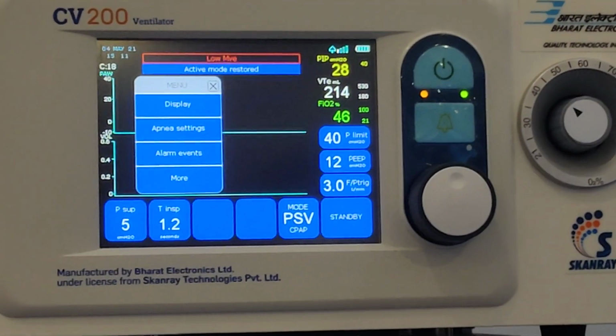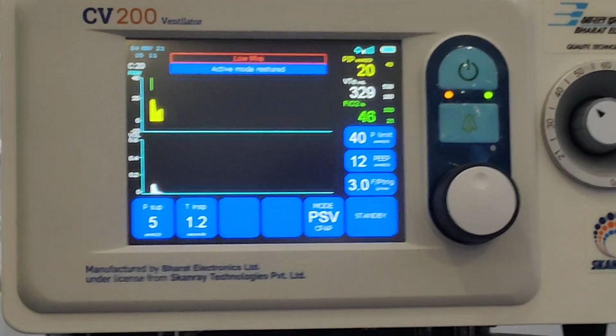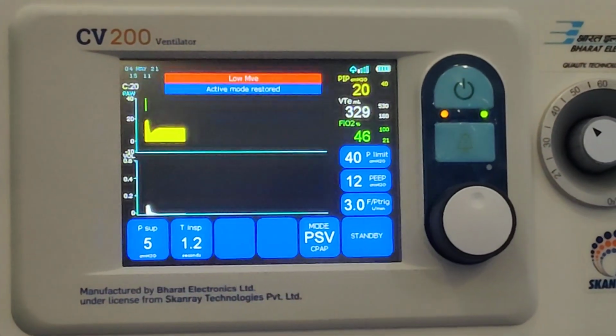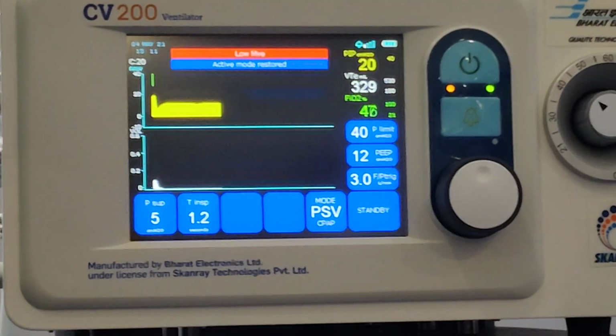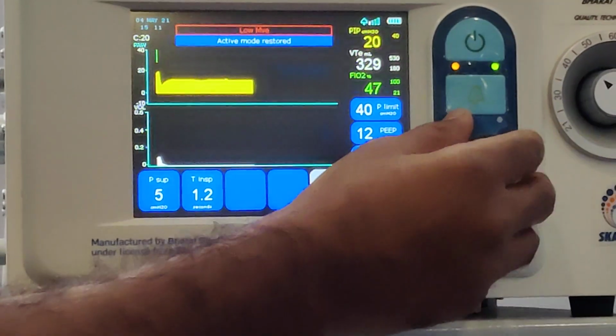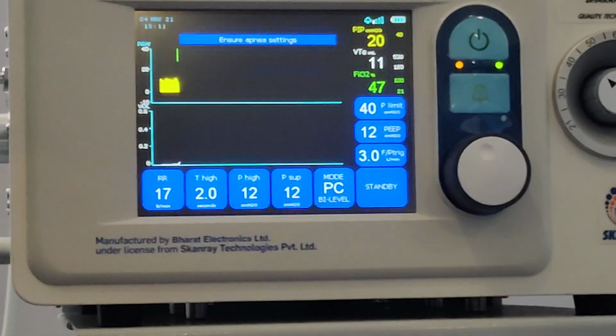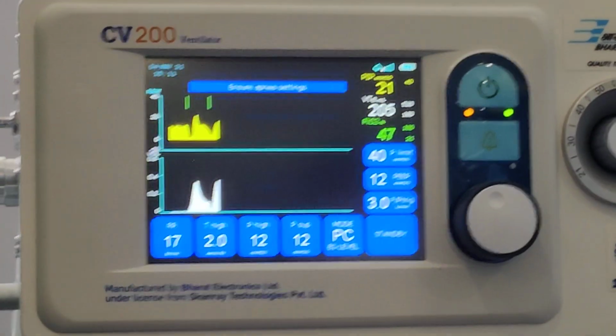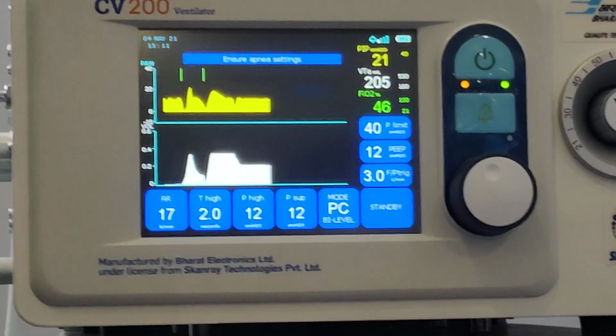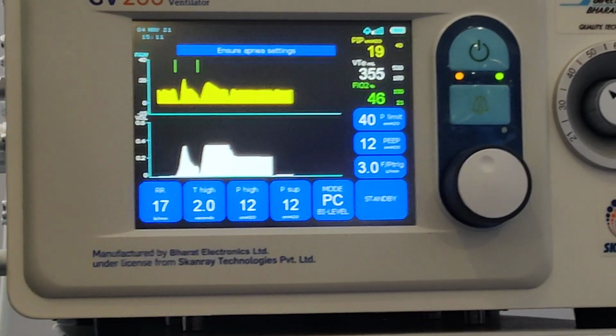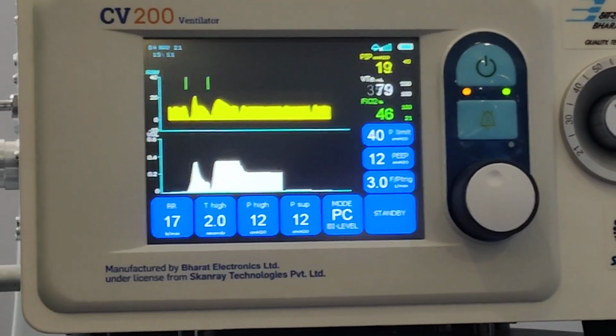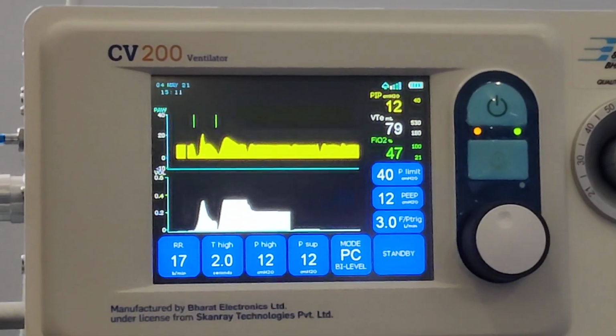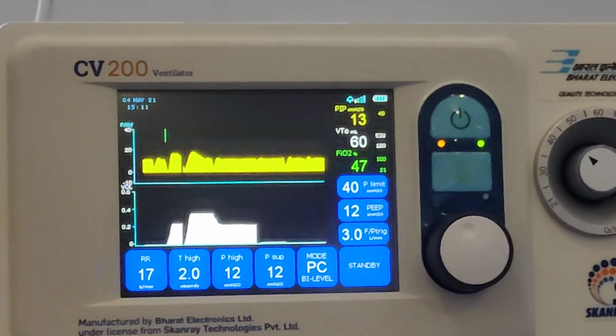So there is a V leak. Sorry, V leak mode. Bi-level mode? What do you want to ask? So this much volume is leaking. A small amount of leak is fine, up to 100, 150 ml. But if most of the volume is leaking, it means your machine is not doing the job.